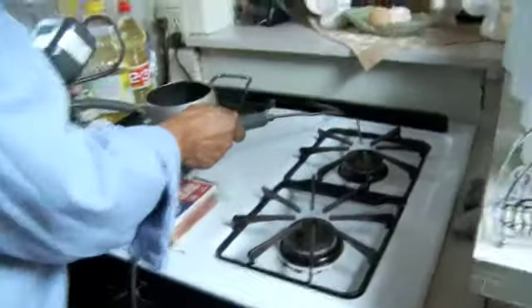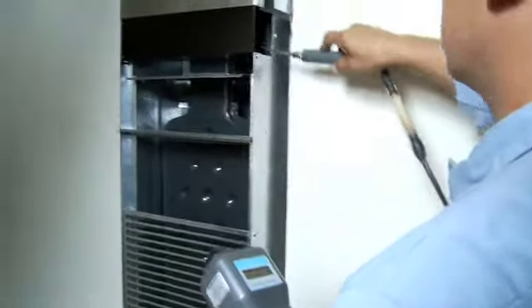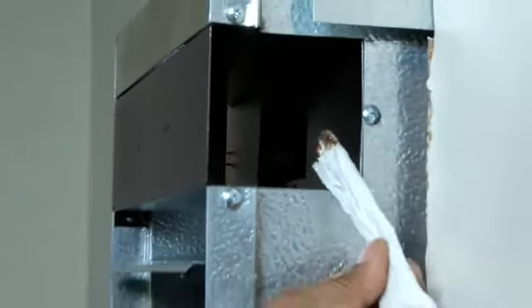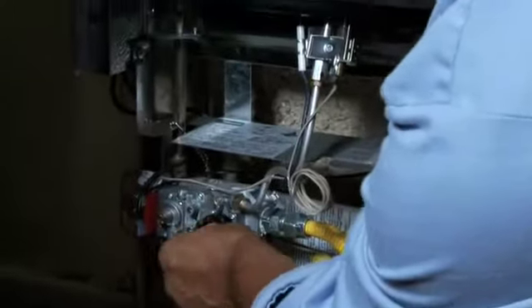During the assessment, a key focus of attention will be the combustion appliances. Any stoves, ovens, space heaters, water heaters, furnaces, fireplaces, dryers, and other pieces of fuel-burning equipment are inspected closely. These appliances may burn natural gas, liquefied petroleum, kerosene, oil, coal, or wood, and will require sensitive detectors to find trouble spots. Combustion appliances are usually safe. However, under certain conditions, they can backdraft, enabling flue gases to spill into the home. These gases pose serious health risk and could even cause death among the occupants of the home. After inspection, the technician will make recommendations to improve combustion appliance safety in every home that gets weatherized.